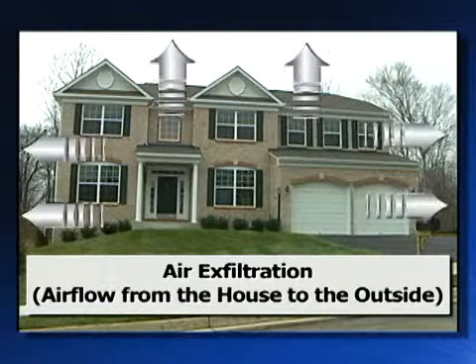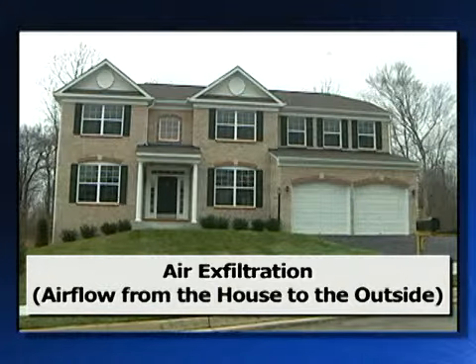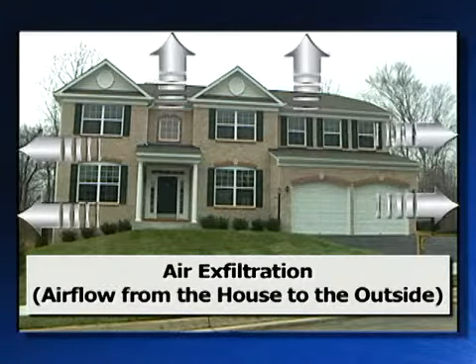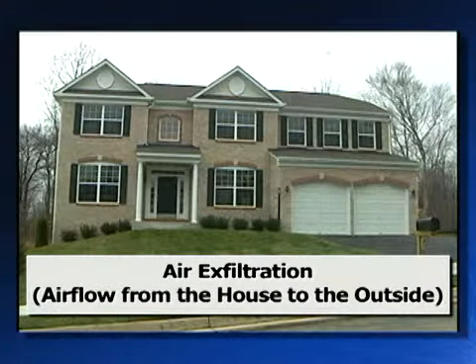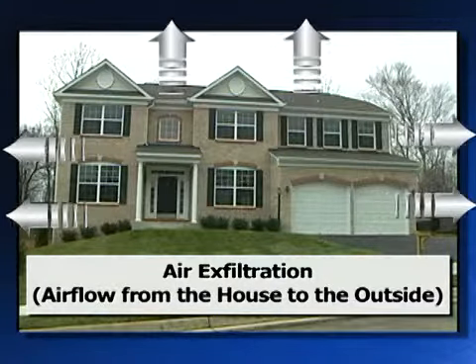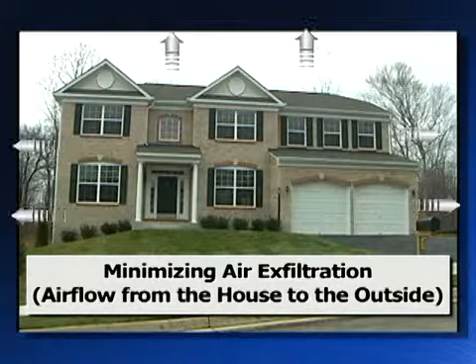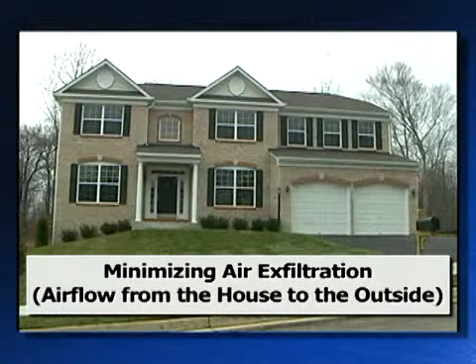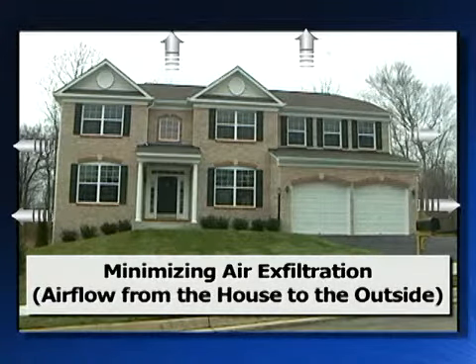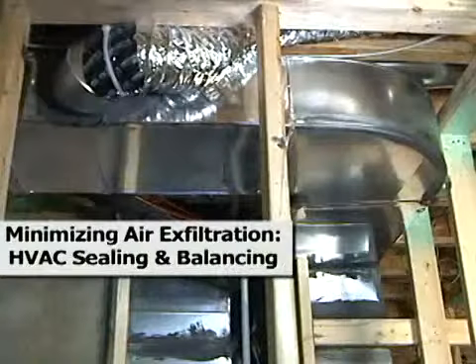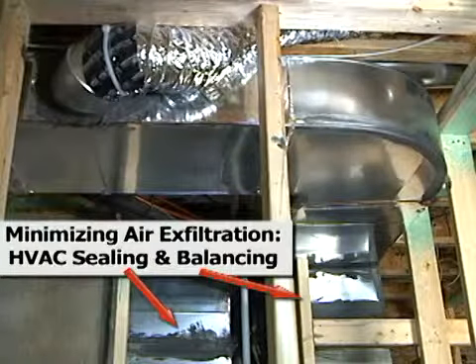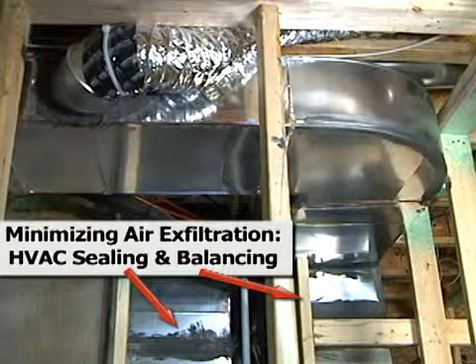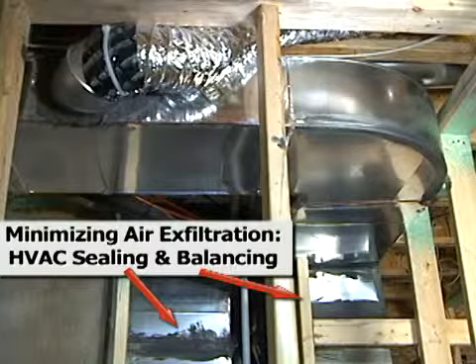Air flowing out of the house is generally called air exfiltration, which is driven by the same factors as infiltration: wind, stack, and the balance of the HVAC system. The air barriers mentioned earlier that reduce air infiltration also minimize air exfiltration. Nonetheless, the HVAC and exhaust systems must be sealed and balanced to minimize the pressures they induce across the building enclosure.